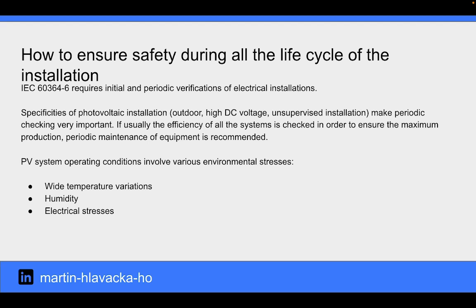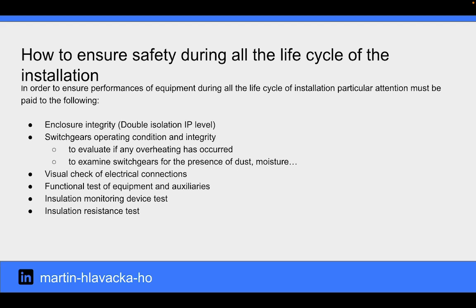PV system operation conditions involve various environmental stresses like wide temperature variations, humidity, and electrical stresses. In order to ensure performances of equipment during all the life cycle of installation, particular attention must be paid to the enclosure integrity, switchgear's operating conditions, and integrity, to evaluate if any overheating has occurred, and to examine switchgears for the presence of dust or moisture. Visual check of electrical connections, functional test of equipment and auxiliaries, insulation monitoring device test, and insulation resistance test.